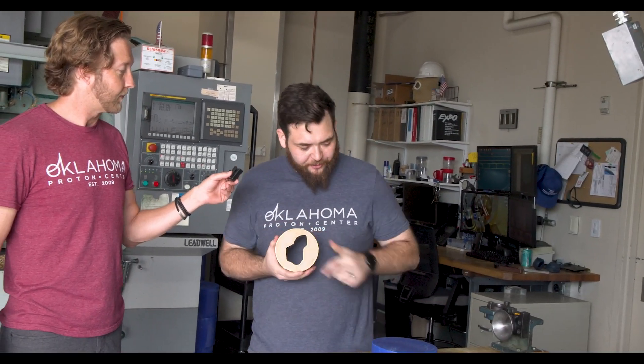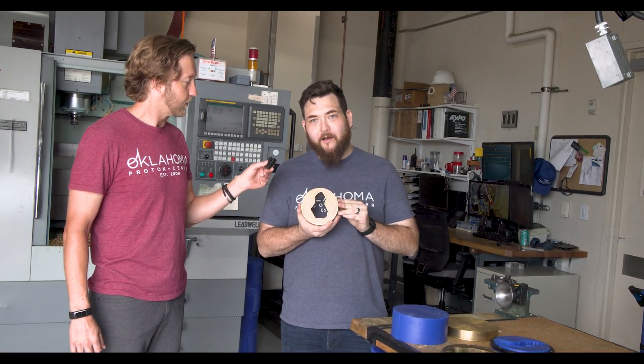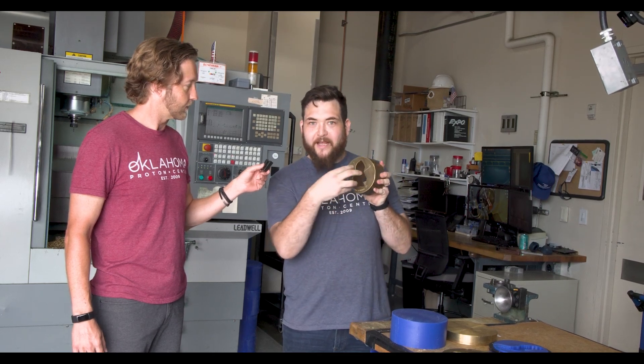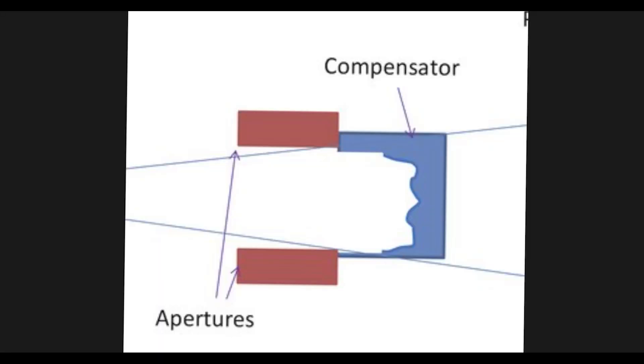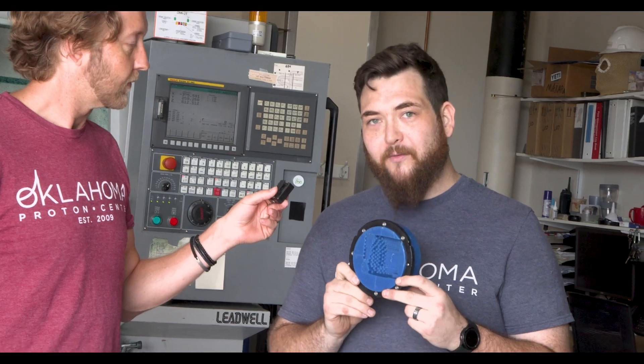In the shop we make the apertures and the compensators that are used for treatment. These are a 2D profile of the treatment area to protect the healthy tissue. Imagine a flashlight hitting this — it protects all the healthy tissue around the treatment area. We also make the wax compensators which depth the radiation, so where they're thinner they'll go farther into the patient, and where they're thicker they'll go shallower into the patient.